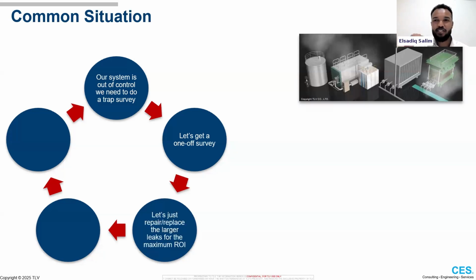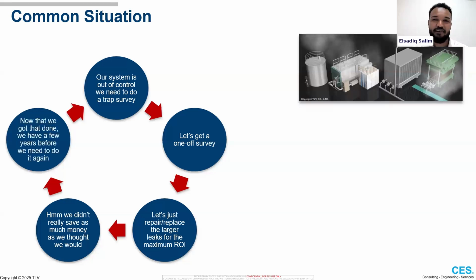Following that, you might have had one yourselves. You get a long list, maybe 200, 300 rows with this steam trap's failed, this steam trap's good, etc. And it can be quite overwhelming to tackle that and to start to maintain replacements. So typically on site, they'll pick and choose: the larger leaks, they'll replace them, or the critical locations, they'll replace them to try and get maximum return on investment. From our experience, often this does not give the maximum savings and it does not give the savings that sites initially think they would, but nevertheless, they've ticked that box, they've had the steam trap survey, which is good.